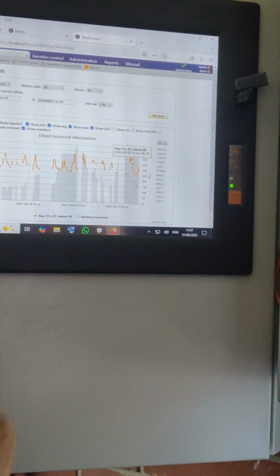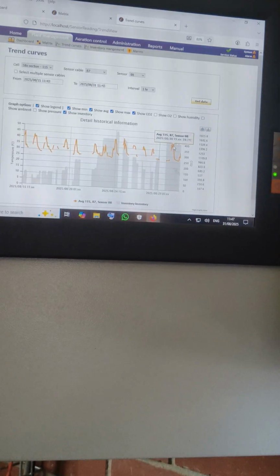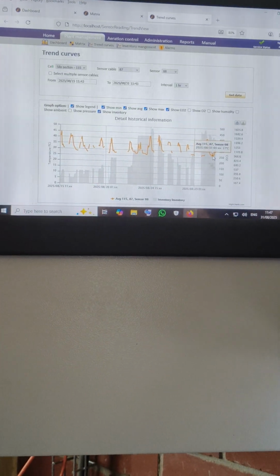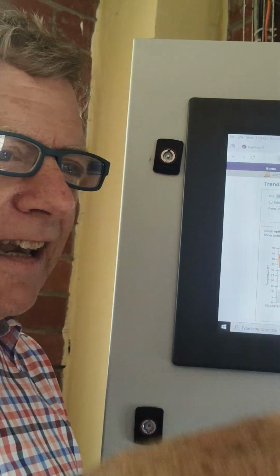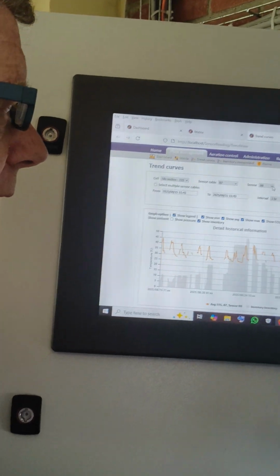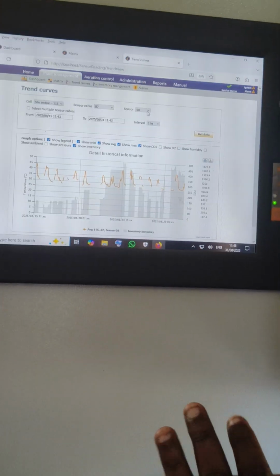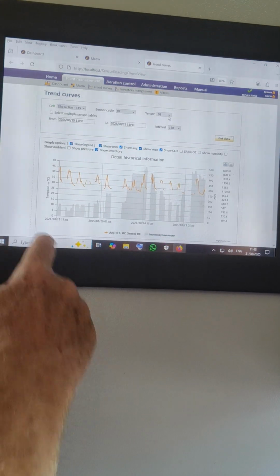Of course it's the top sensor. So yesterday we went up to 40 degrees on this sensor, and in the morning at 3 o'clock we were down to 27. So this is also how the sensor will know, am I in the grain or not? He will say, what is it at the night, what is it at the day? And if it's the same, then he will say, okay, I'm inside. So this fluctuation is not a problem. Day and night temperature, it's very useful. We can see that we are not in the grain. This is normal.